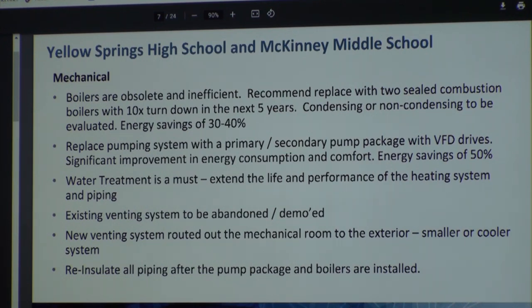What we'd do is size the boiler - let's say your worst case heating load is 3 million BTUs on the coldest day of the year, just for the sake of it. I would size one boiler to be like 2 million or 2.2 million BTUs, because the worst days are only about 10 days a year.